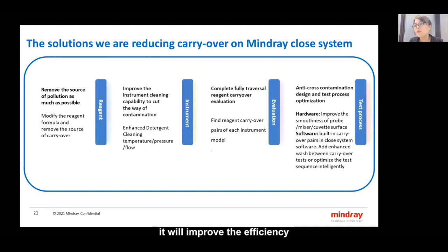So if we can use a closed system, it will improve the efficiency and reduce the carryover issues. Okay, let's make a summary together. First, carryover itself is difficult to detect. Usually, we need to do a lot of verification tests to find the reason. And we can improve the performance and reduce the carryover with optimized design and full evaluation. This is today's sharing. Thank you.